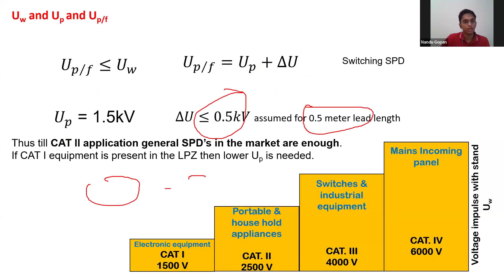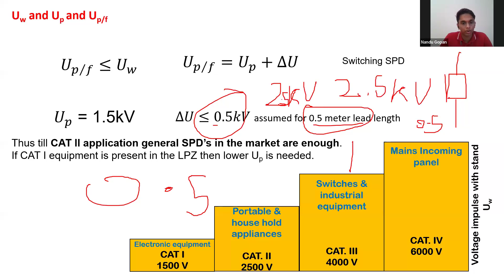And this delta U is actually related to the lead length. I am highlighting this more: you should have a lead length of less than 0.5 meter. Lead length means you have an SPD and you have a wire here. So this should be less than 0.5 meter. Then delta U will be around 0.5 kV, and UP by F will be around 2 kV, which is less than 2.5 kV. So it is good. But if you have a lead length of more than 1 meter, then delta U will be much more than 0.5 kV. That means there is going to be no protection. So I'll just skip it.